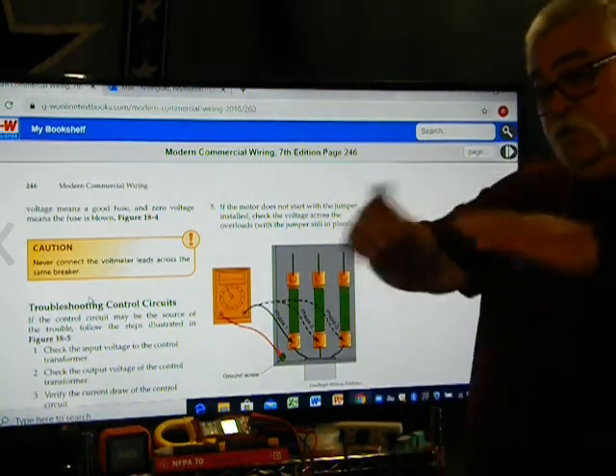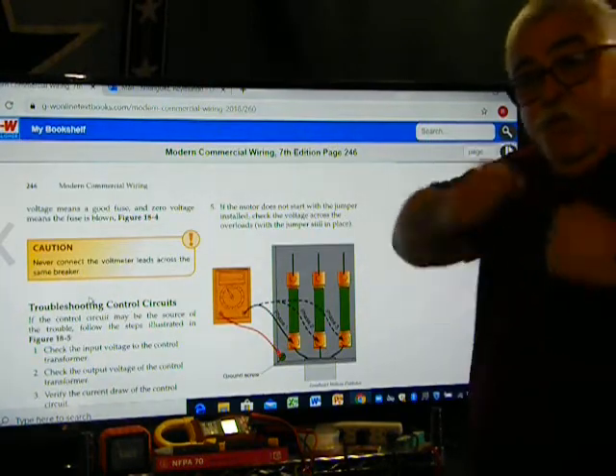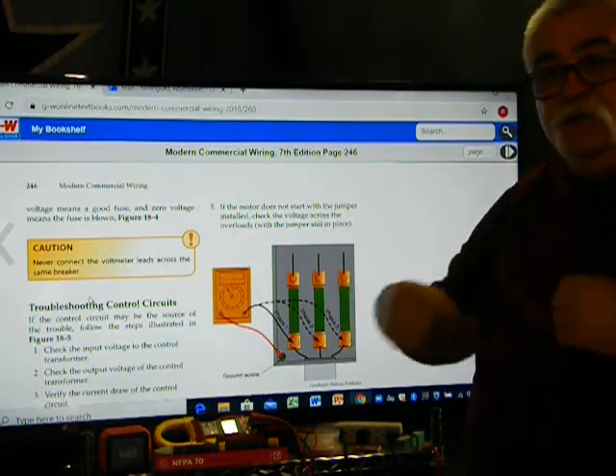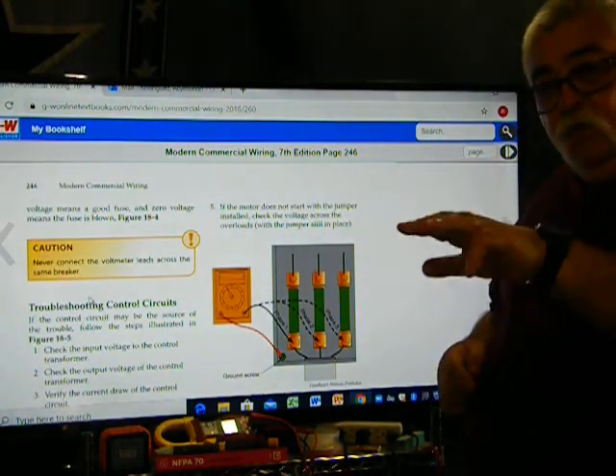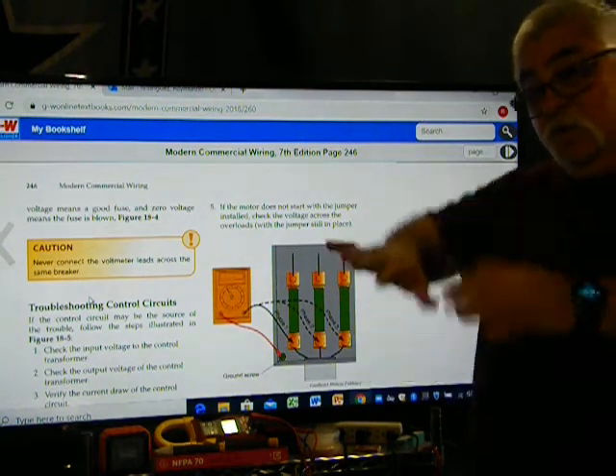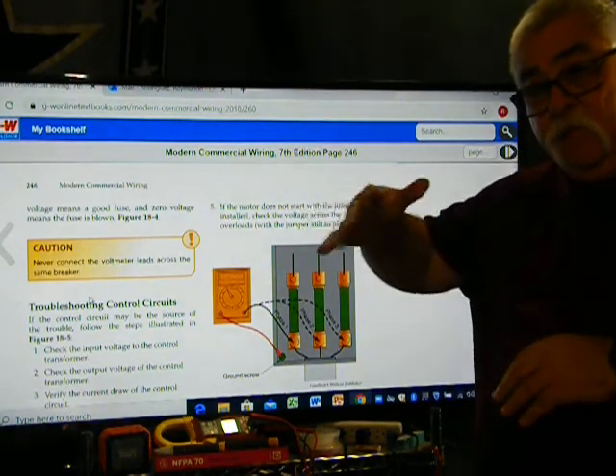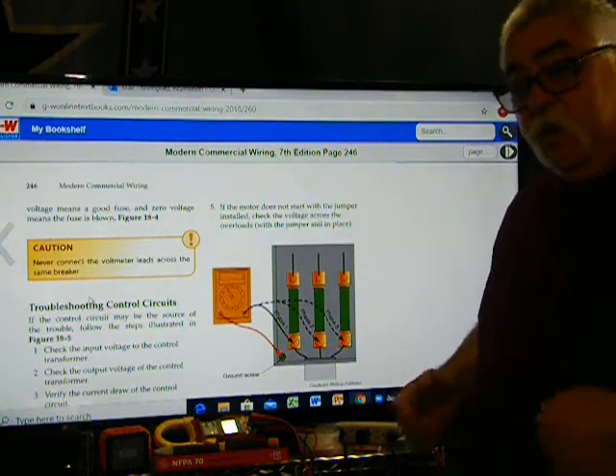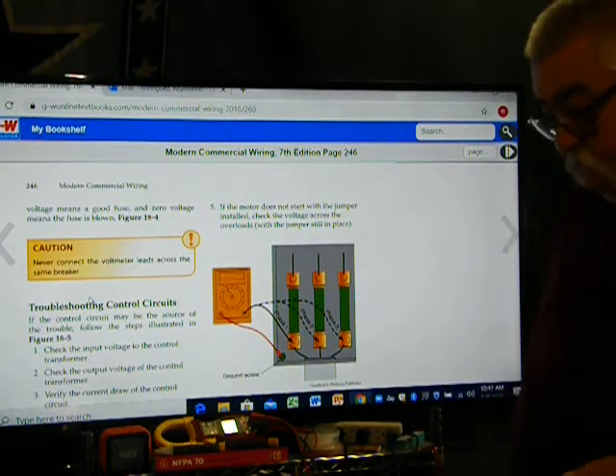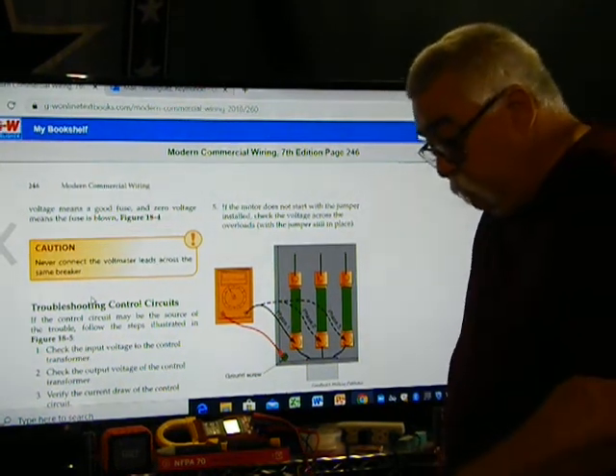So what happens is the motor is kind of doing this. Why? Because it's not running balanced. I don't have the voltage across the three windings, so the motor starts wobbling. It can start vibrating, can cause problems, and the motor overheats. It can be excessive loading.